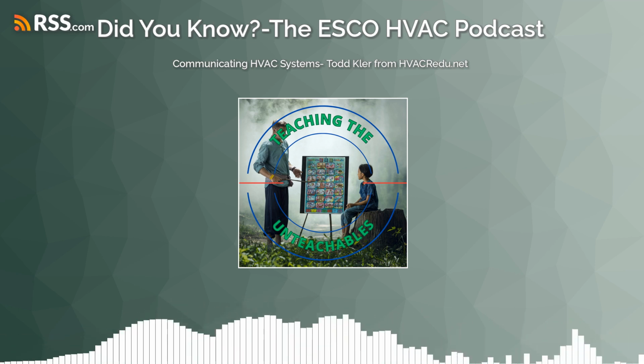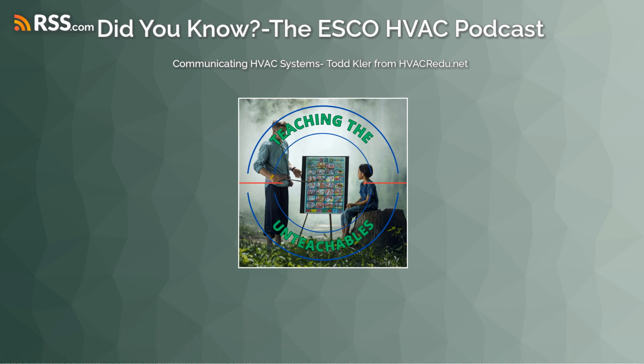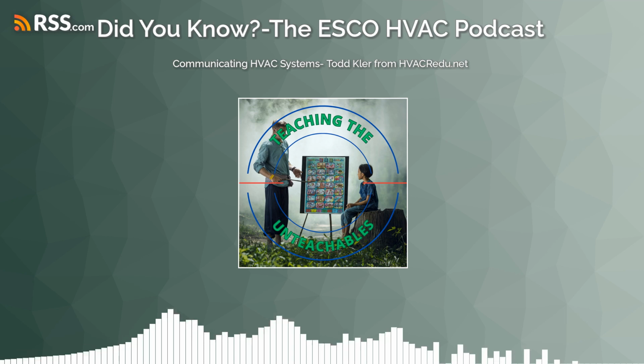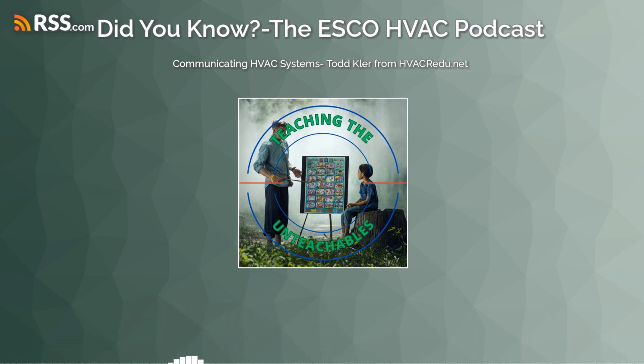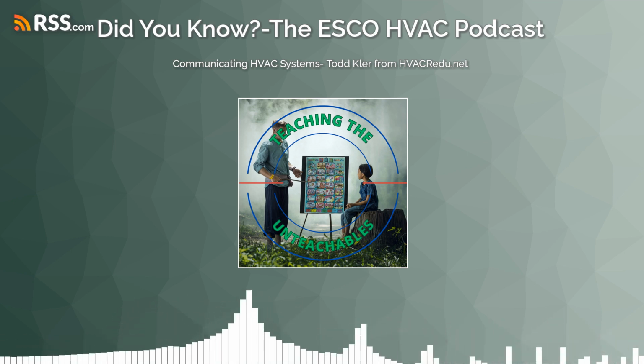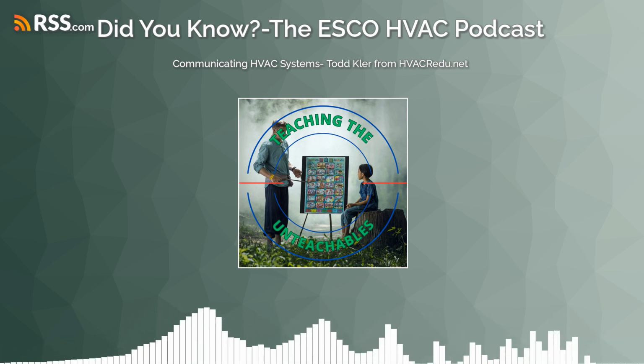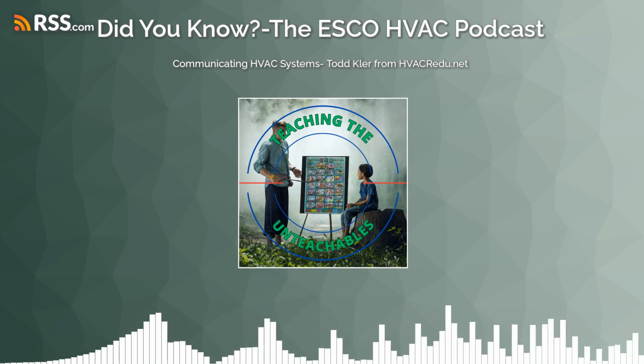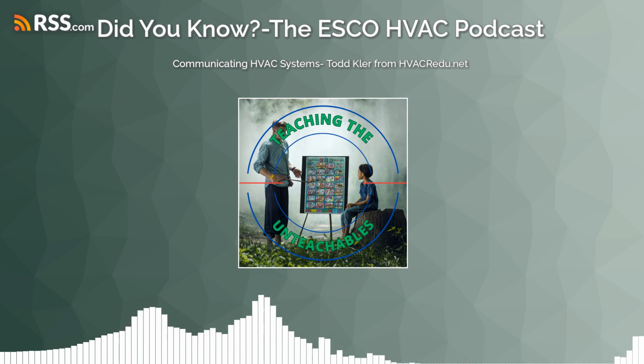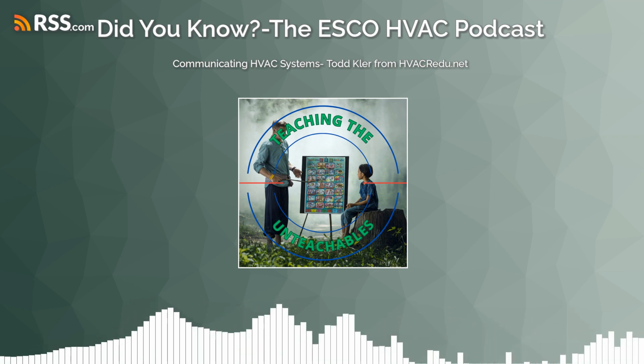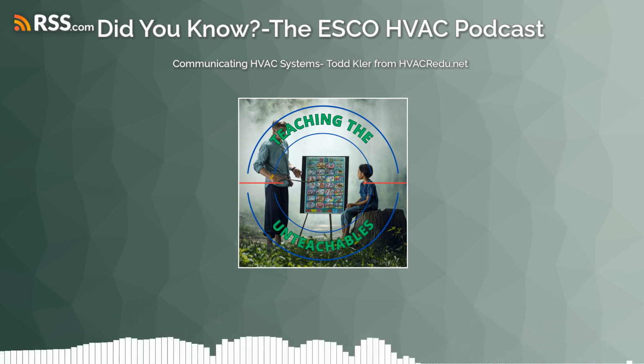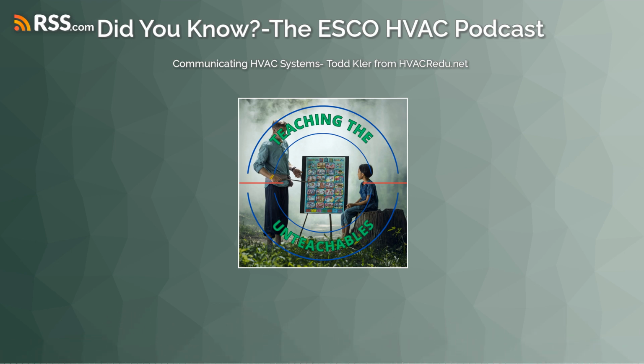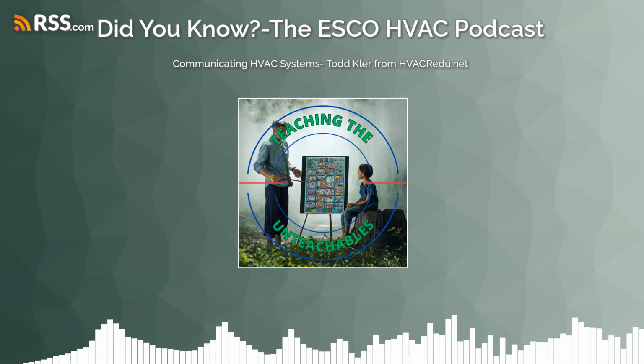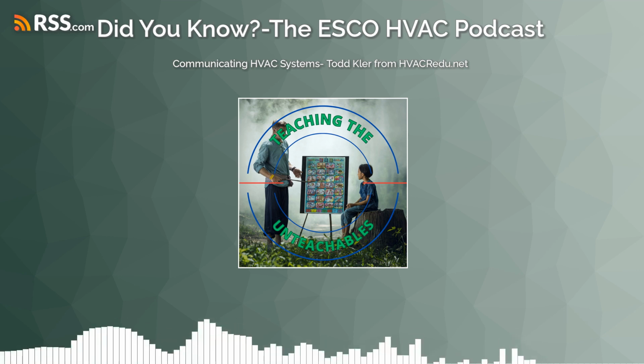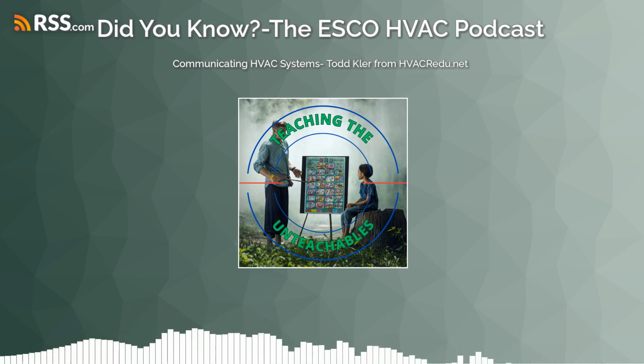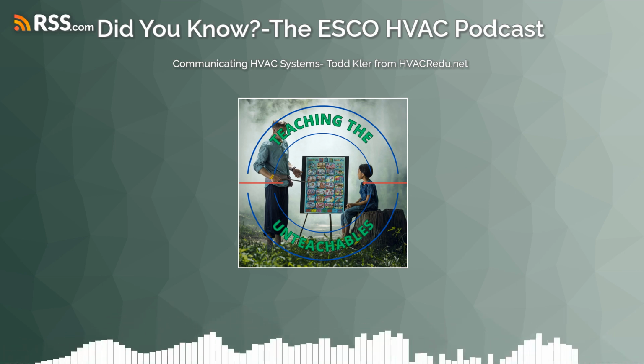And there's a difference between the two of them that we're going to call the bias. So with this particular system, this Climate Talk system that we're using with Daikin and some of the earlier Goodman Amana stuff, we are going to be able to measure from ground to number 1 and from ground to number 2 and get 2 different voltages. And what a lot of people don't realize is that difference between them, that bias, is actually our bandwidth. So about a year ago, I did a class with John Brown over at EWC where we went really deep into this exactly. So if you want to learn more about that, on this finished edited video, I'll make sure to put a reference to get back to that one so you can understand what that entire bandwidth looks like, how to set the bias, and if your bandwidth's not good, how you adjust that. But for today, we're not going to go that deep. I just want you to understand that when you're looking at that, we actually have those signals above ground and below ground in reference. So some positive, some that are actually negative.